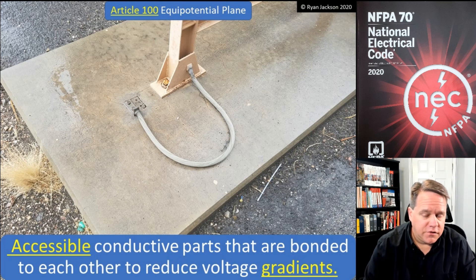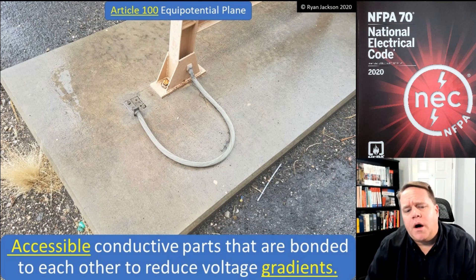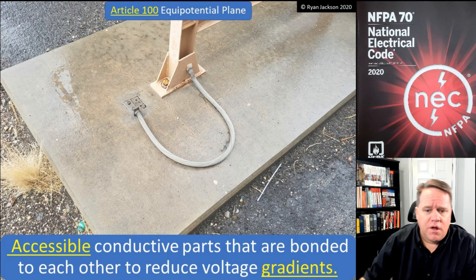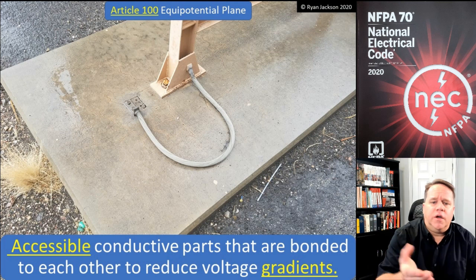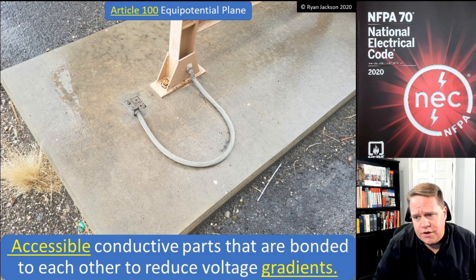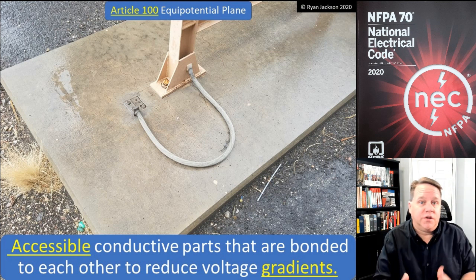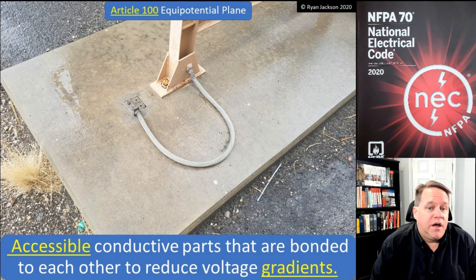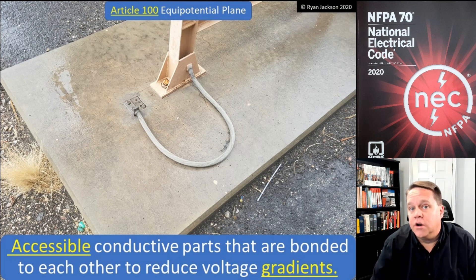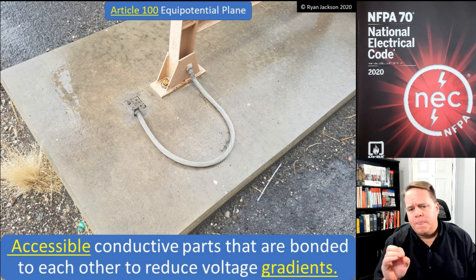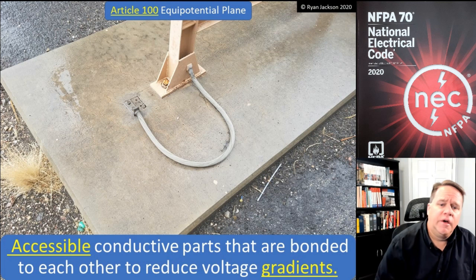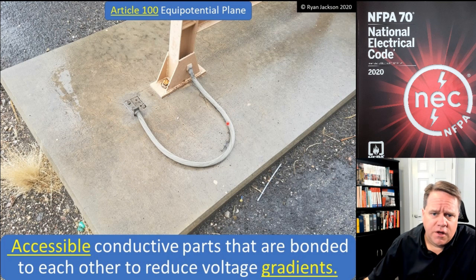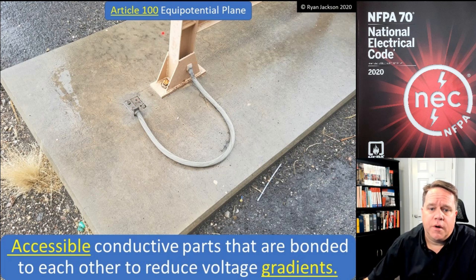The definition is: accessible conductive parts that are bonded to each other to reduce voltage gradients. The term 'accessible' was added, which may have been a mistake. Is concrete conductive? We don't consider concrete a conductor intentionally, but if you're standing barefoot on concrete contacting earth and you touch a live wire, you're going to get shocked — so it does conduct electricity. Looking at the picture here, this is medium voltage equipment where the support structure is bonded to a section of concrete.